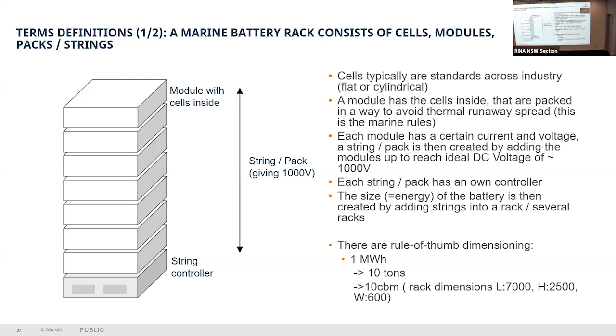Each module has a certain current and voltage. A string pack is then created by adding the modules up to reach the ideal DC voltage of 1000 volts. Each string pack has its own controller. The size of the battery is then created by adding strings into a rack. There is a rule of thumb if you have to dimension it: for 1 megawatt hour of batteries, it's close to 10 tons and 10 cubic meters. The rack dimension could be 7 meters by 2.5 by 0.6. You can see the figure here on the left-hand side, how it looks.